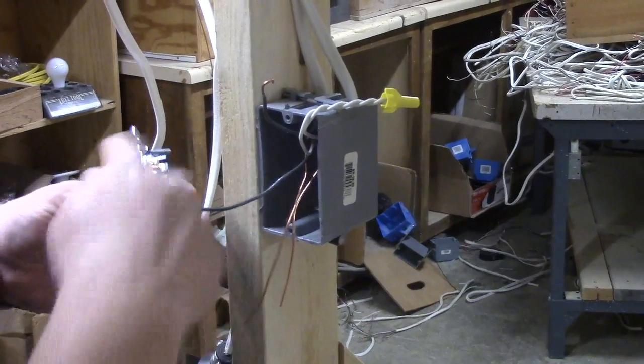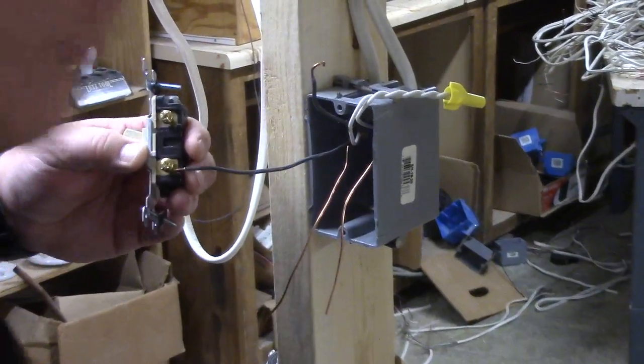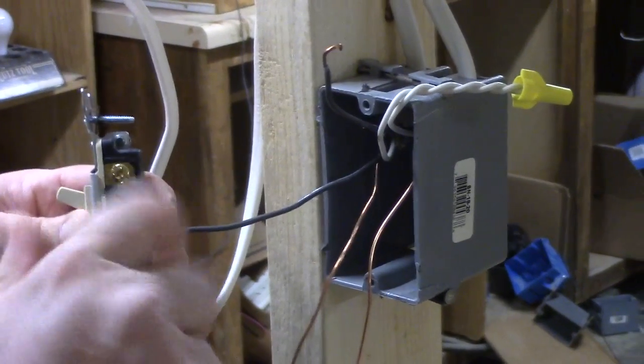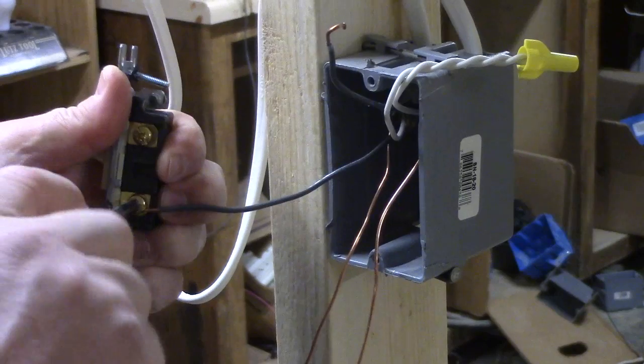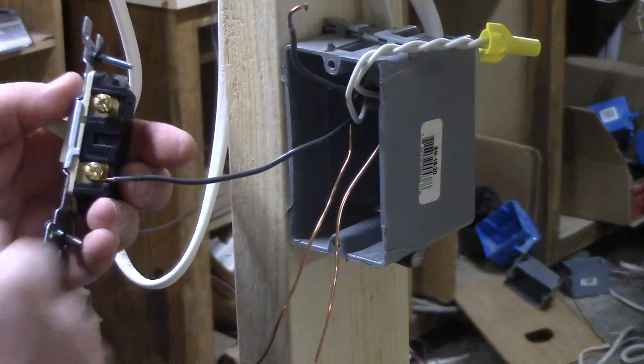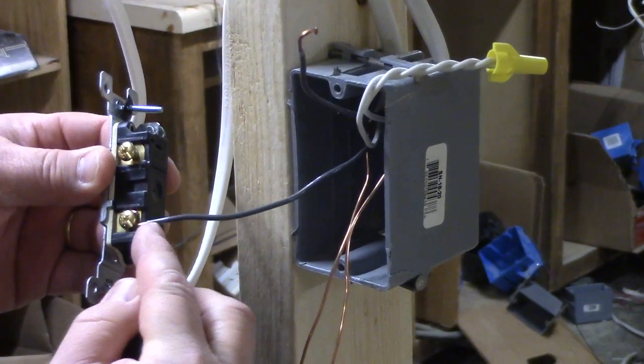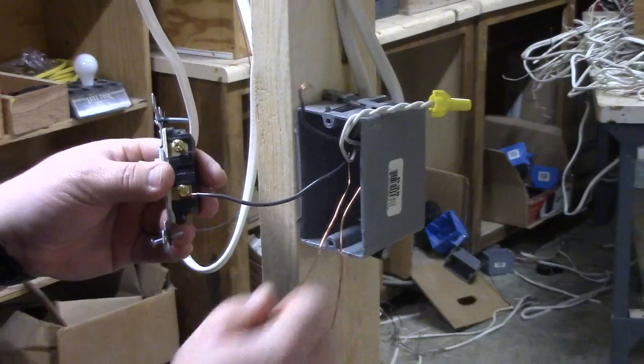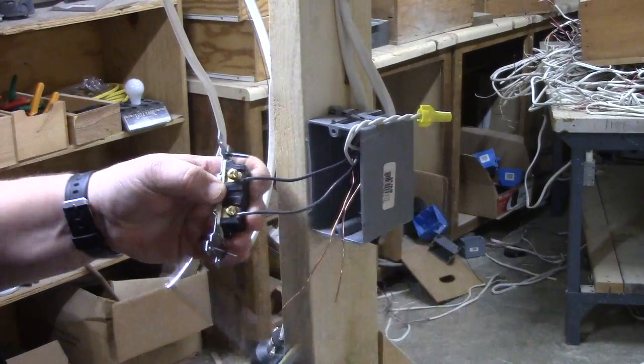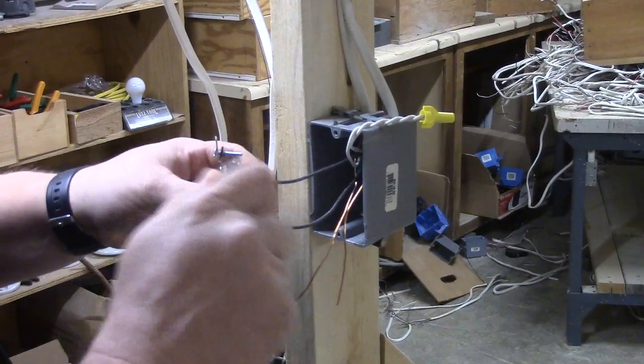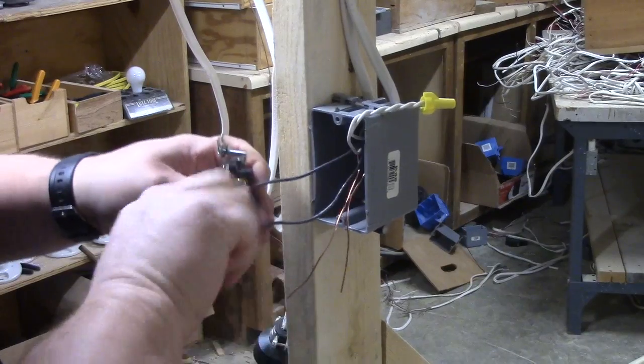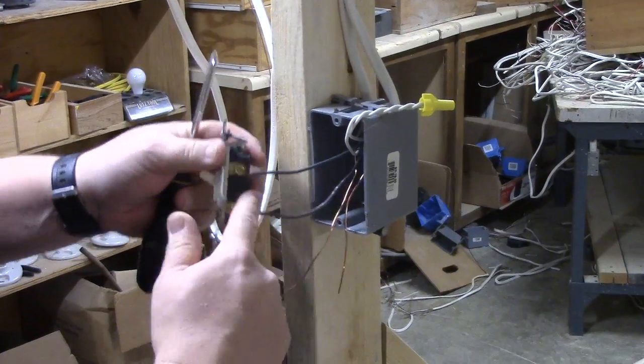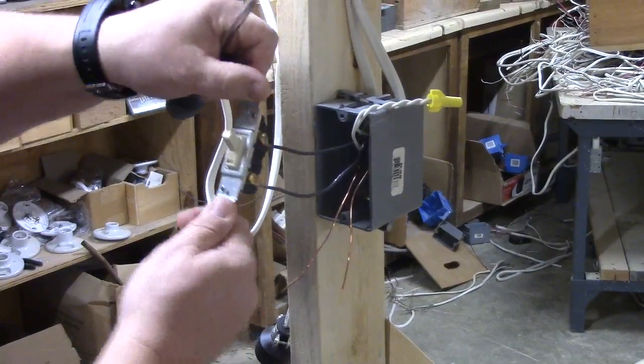I've got my electricity coming in. I want my J-hooks to go clockwise around the screw head. This reason is when we tighten this screw down, it's turning clockwise. It will grab the wire and really tighten with it. As you can see, it just squeezes it on down. Now my J-hook isn't too long. I don't want this to be stripped way back here, because the possibility is when we put it back in here, we don't want it rubbing up against the ground and shorting out. We're going to hook up the other one going out to our light. Tighten it down nice and snug. As you see, it twists it around too and pulled it up right there. We're done. We now have our connections pretty much like we just broke the wire in half and attached a switch to it.